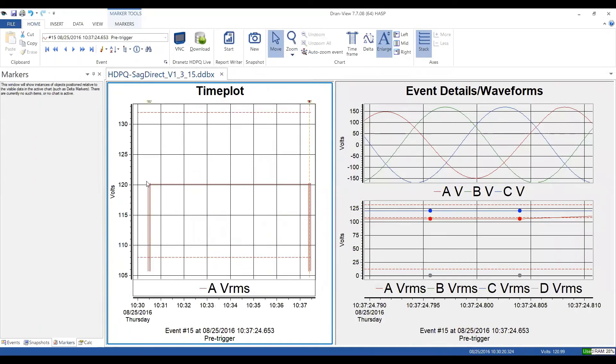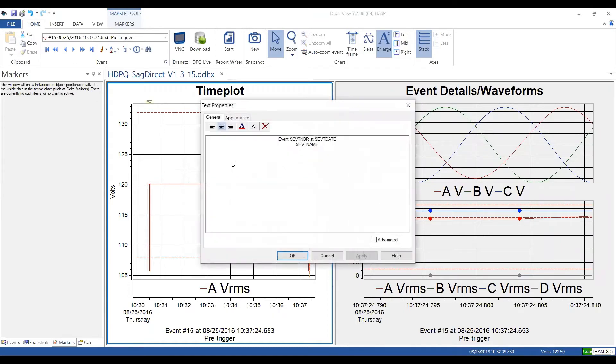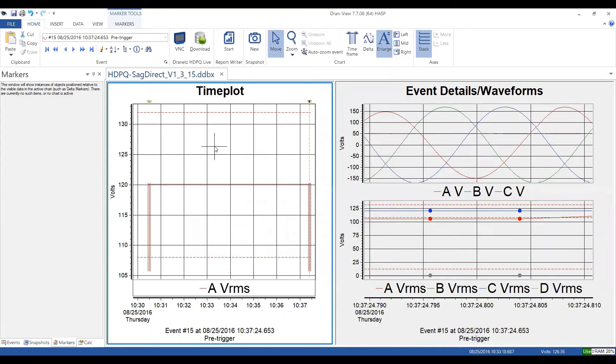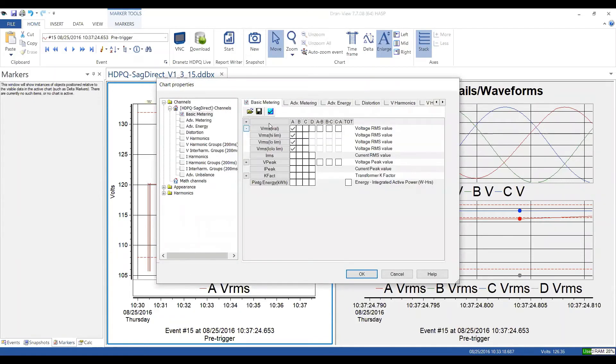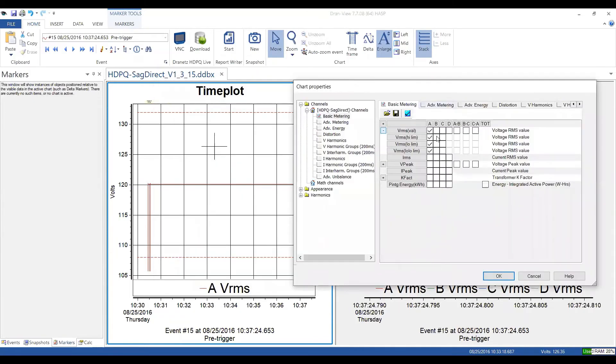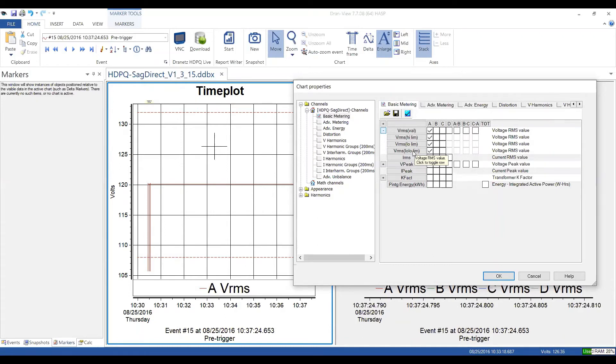Just to describe, I have my voltage being plotted. I have my high limit. I have my low limit. So when we go back to the properties, we go back to the properties and I expand here. You can see I've got my high limit, my low limit. And with the low limit, it's an interruption threshold that's set up by the instrument. That's usually about 10% of the nominal.